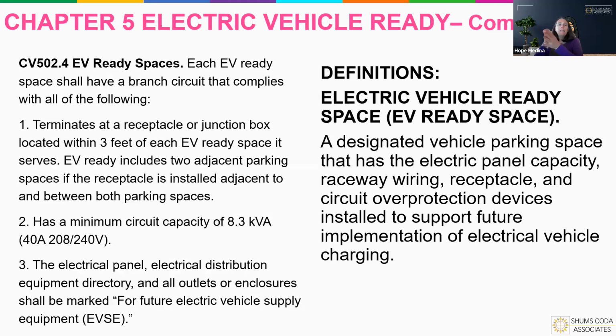If we're doing EV ready, it means that it's going to terminate at the receptacle or junction box. It needs to be within 3 feet of the space, and it can do both. I believe it has the junction box or receptacle instead of just having it capped off. It has the space so that all they have to do is either plug the equipment in, or take the plate off, add the plug, and plug the equipment in. That's basically what they're looking at for the EV ready space.